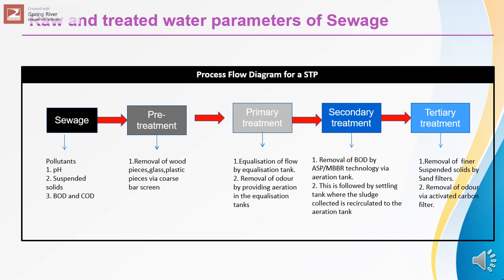Then it moves to the primary treatment system, where the flow is equalized and odor is removed by providing aeration in the equalization tank. Then it moves to the secondary treatment system, where the BOD is removed by various technologies like activated sludge process (ASP), moving bed bioreactor (MBBR), membrane bioreactor (MBR), and sequential batch reactor (SBR). In this course, we are going to concentrate on ASP and MBBR.